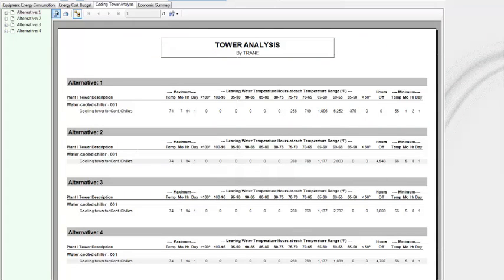I want to point out that the Cooling Tower Analysis Report shows only tower hours coincident with chiller operation. Clearly, the tower is running more in free cooling modes — it's just not reflected in this report. But since the tower is shown as off more hours in the free cooling alternatives on this report, it can be inferred that the chiller itself is running fewer hours as well.